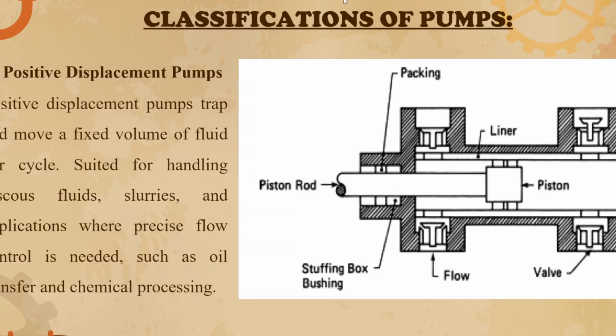Next is the positive displacement pump. It traps and moves a fixed volume of fluid per cycle, suited for handling viscous fluids, slurries, and applications where precise flow control is needed, such as oil transfer and chemical processing. So this is the positive displacement pump.